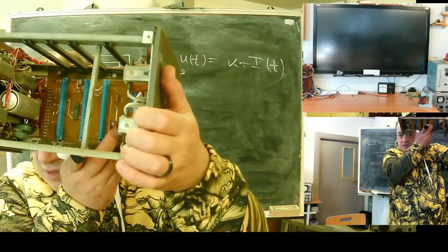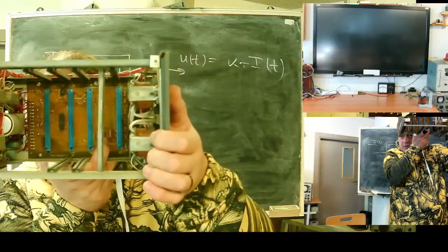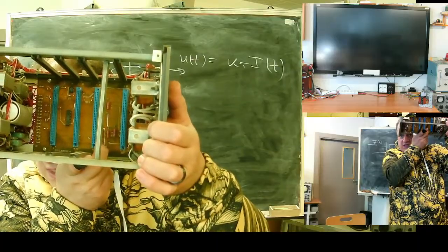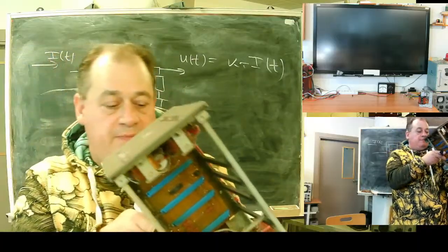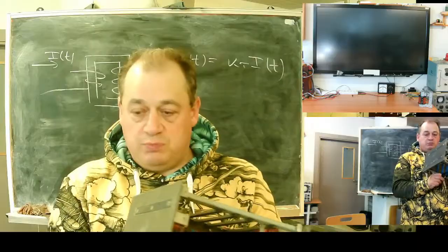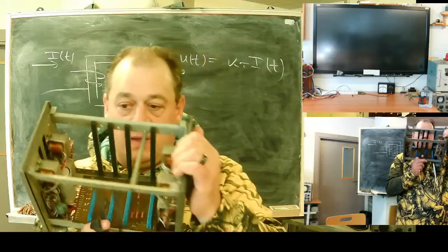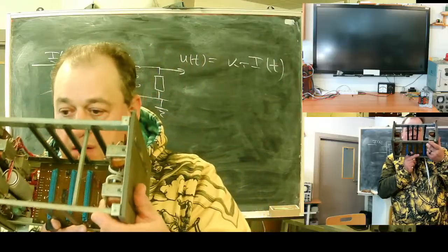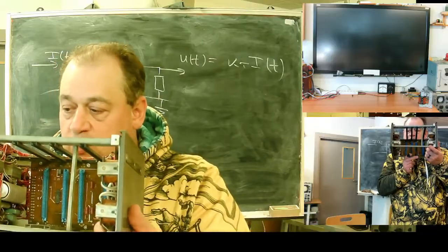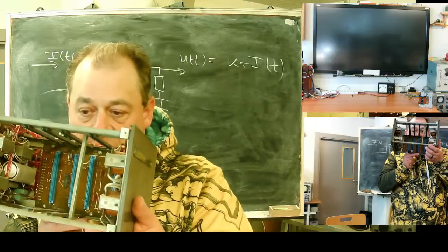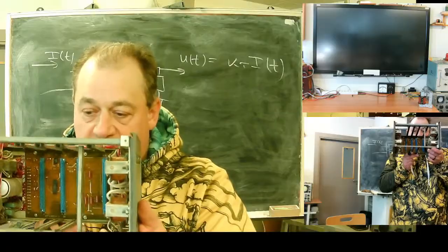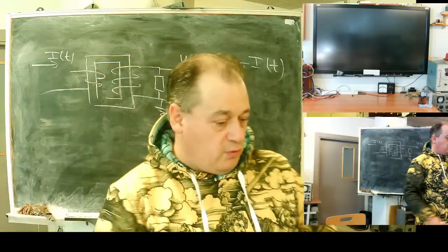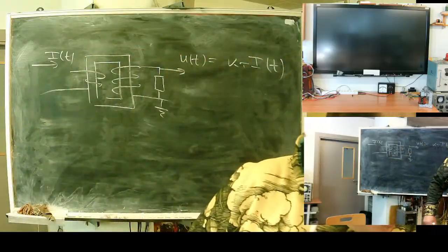Can you see this? Oh, no, you can. These small red ones are load resistors. Current transformers should be loaded. Here, you see. Medium size, set of 3 current transformers.